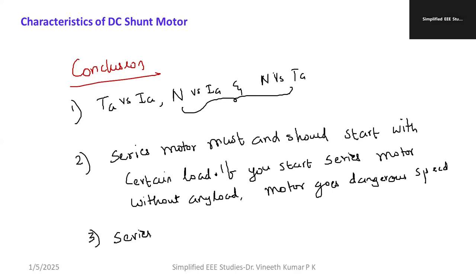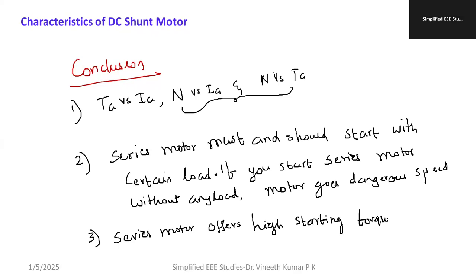Another important inference: a series motor usually offers high starting torque. So it is most appropriate for heavy load applications, especially cranes, hoists, and conveyors. These are the inferences we can make from the characteristics of the DC series motor.